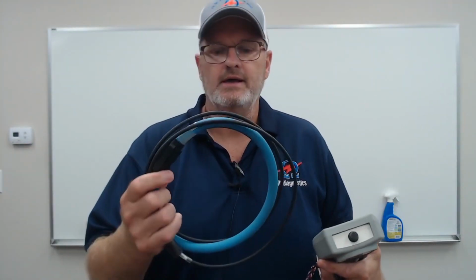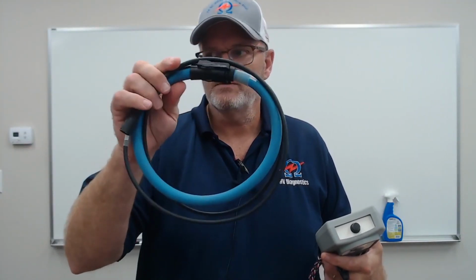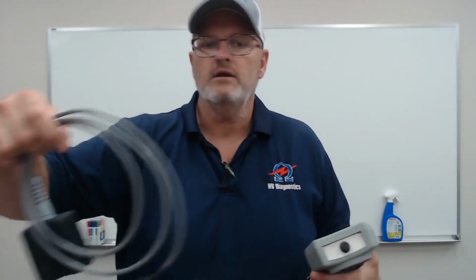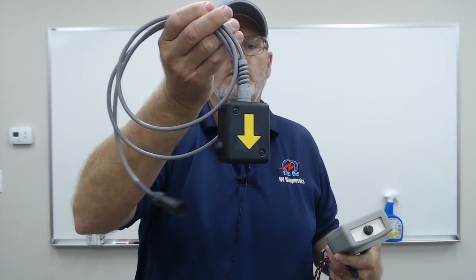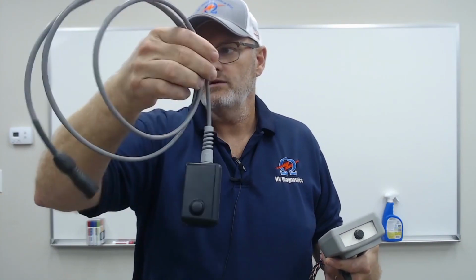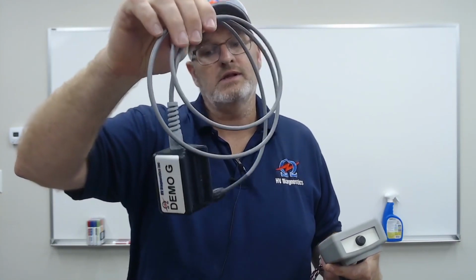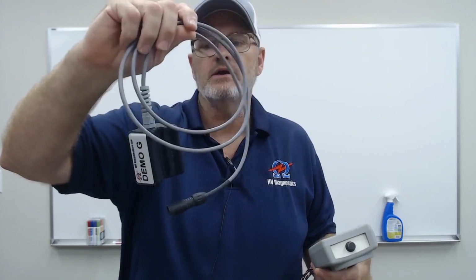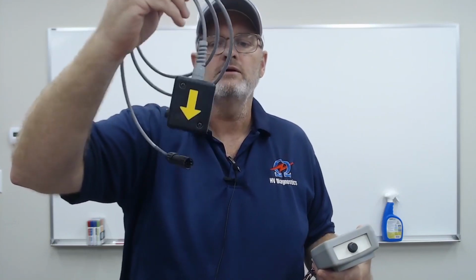Likewise, it has a connector over here where you can connect different types of transducers. We have the one over here, which is the Rogowski coil. That is used for single-phase cables. And then we also have another one, which is the pickup coil, as we call it, the puck, which you can use around single-core cables as well as a secondary test, but primarily used for three-conductor cables.